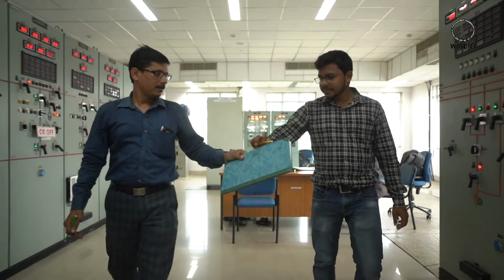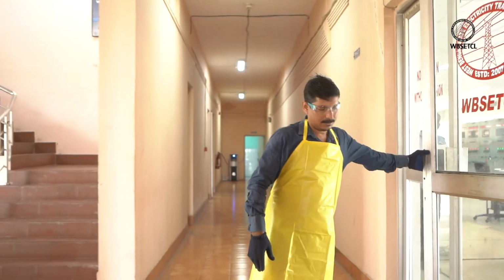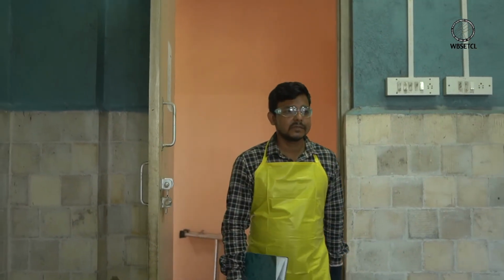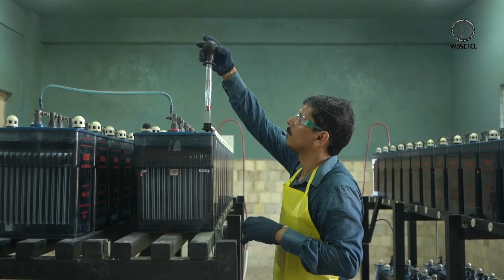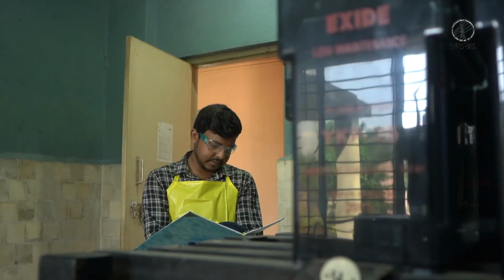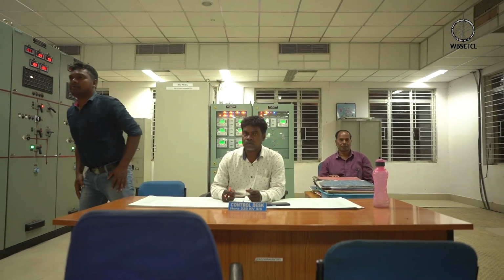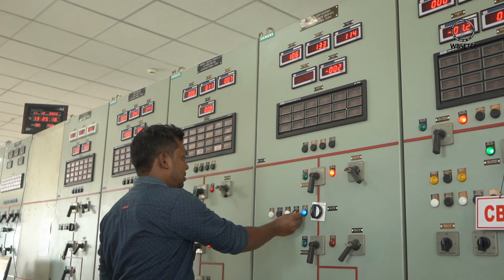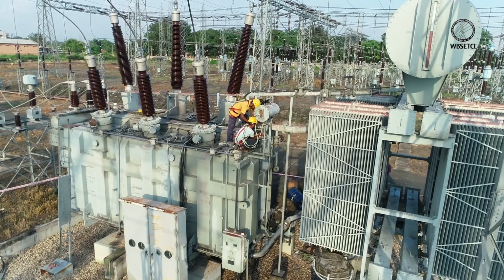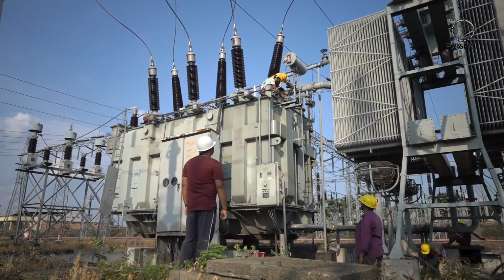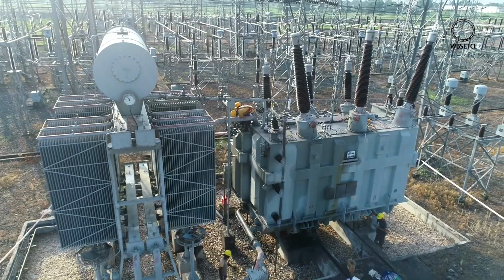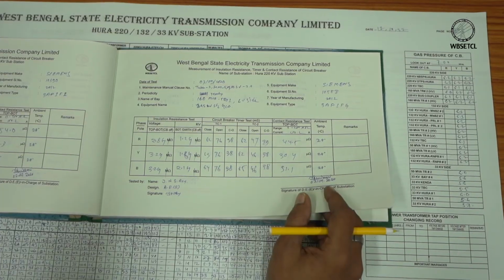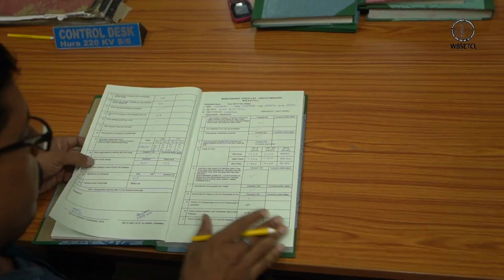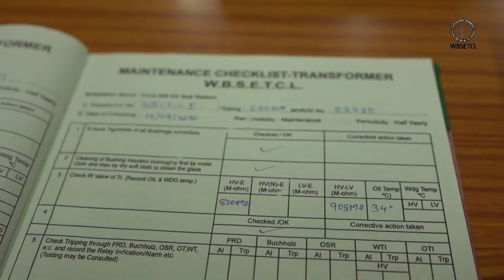The entire DC system is well maintained at site with timely cleaning of batteries, distilled water topping up and specific gravity measurements. As per maintenance schedule, condition-based monitoring of EHV equipment has been adopted with an ultimate aim to reduce operation and maintenance cost.